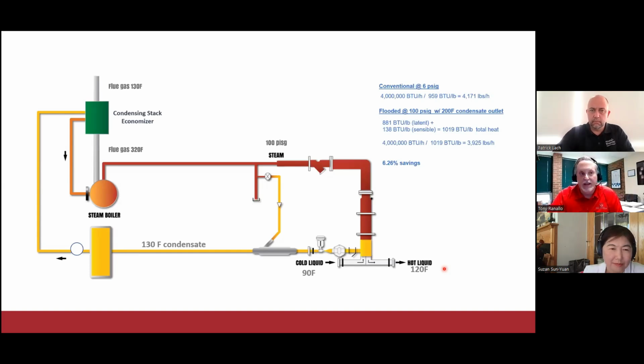If we do that with a flooded heat exchanger with 100-pound steam, now again, we don't have to have the PRV stations on the inlet side. We can take that pressure directly into our system. And if we design it for a 200-degree maximum condensate outlet temperature, we only need 881 BTUs per pound of latent heat, because we're also going to pick up 138 BTU per pound of sensible heat, which gives us a total heat of 1,019. Do the math, comes up with 3,925 pounds, which is a 6.26% savings in steam.